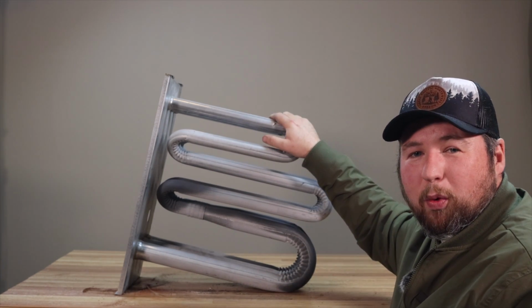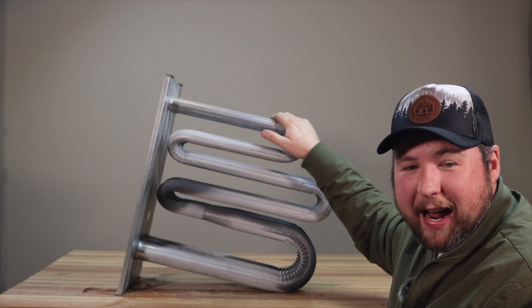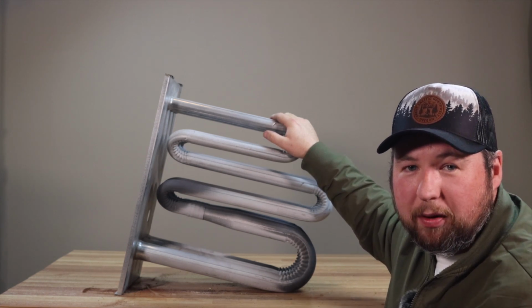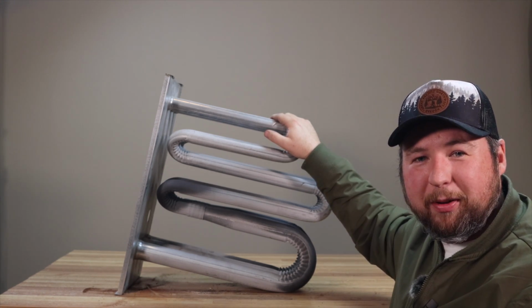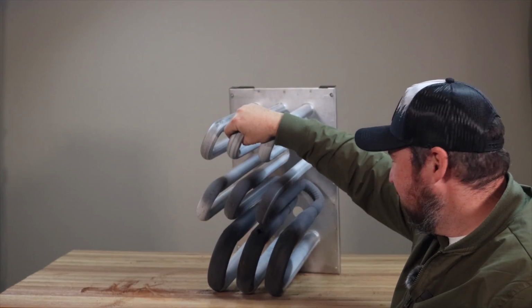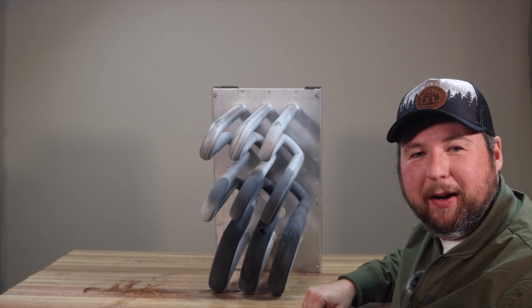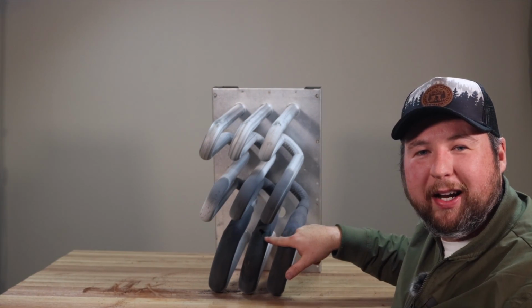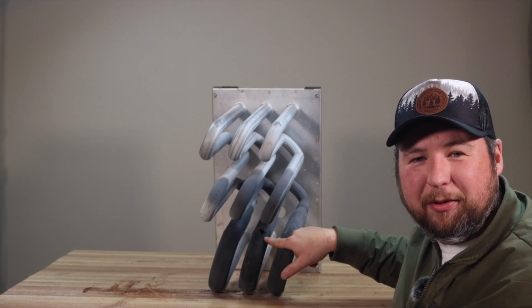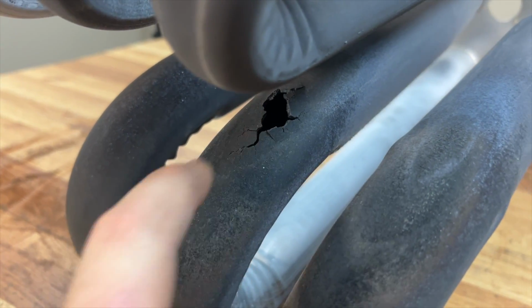So, worst case scenario, you can have large cracks or you can have holes. Let's show you what that looks like. I don't know if this shows up on camera, but there is a massive hole right here. So let's go ahead and get a closer look at that. Here's our massive hole on this heat exchanger. So what caused that? Well, it started off as a little crack and then just got way bigger. So obviously this was missed quite a few times.